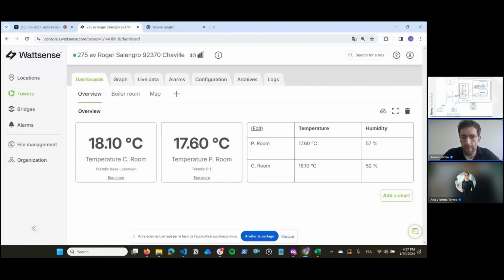We finally made available data persistence when we restart the application. This means that when you have a gateway, a Modbus or a BACnet gateway, and you redirect the value of a data point - before, when the box was restarting or there was a software update, a zero value was sent to the gateway, so to the BMS most of the time, which was a problem for the BMS, and we understood it. Now, when the box restarts, we will send back the latest value before the box restarted to the BMS, so that you don't start from zero - you start with the latest value, and then at the next reading you get a new value, and so on. This is a big announcement for us.